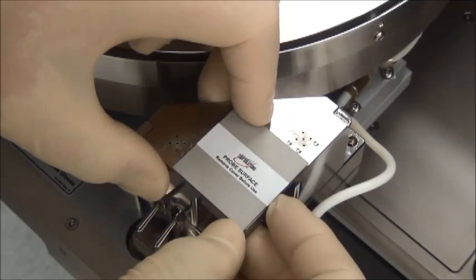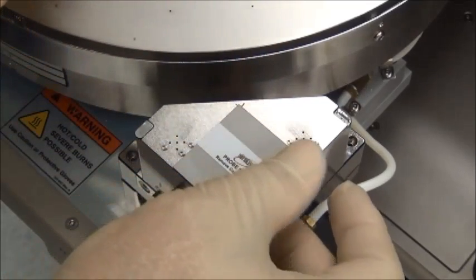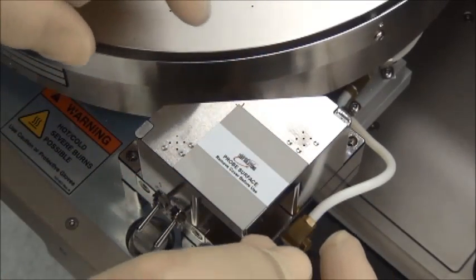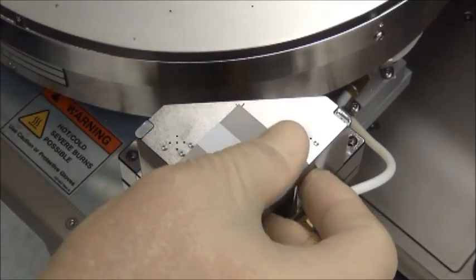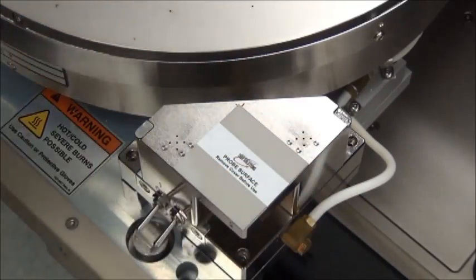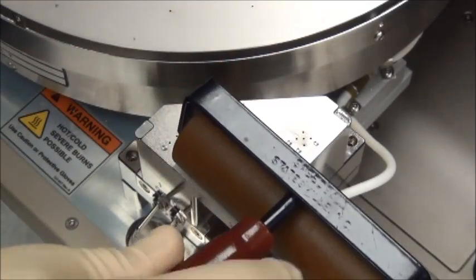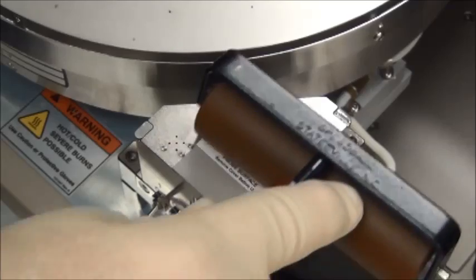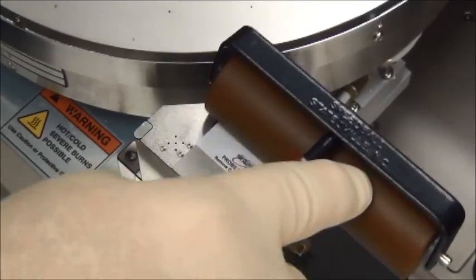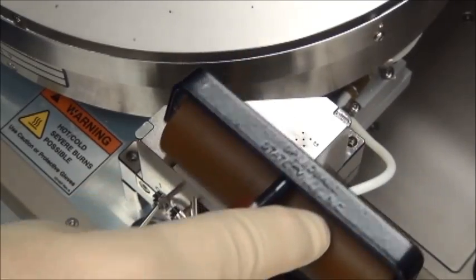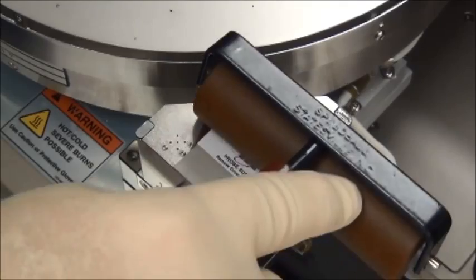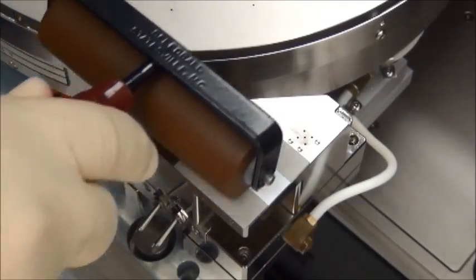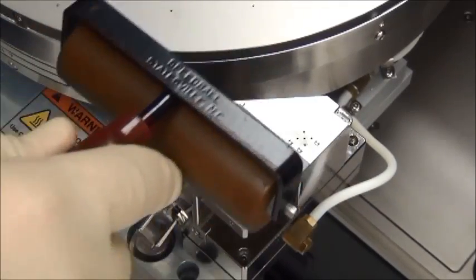Then, starting from the center and working outwardly, uniformly apply gentle pressure to the top of the pad to secure the pad in place. The goal here is to make sure there are no wrinkles and no air bubbles captured in the center of the pad. Then using a hard surface roller with moderate pressure, work out any air bubbles to finish adhering the pad to the chuck surface.